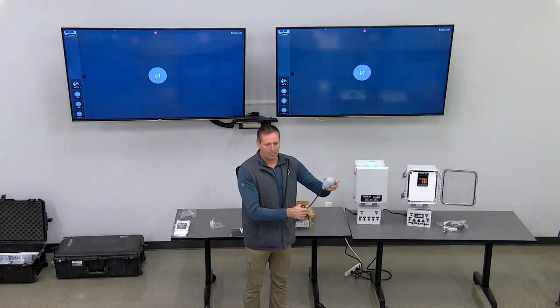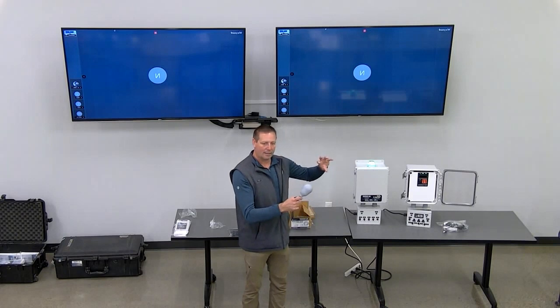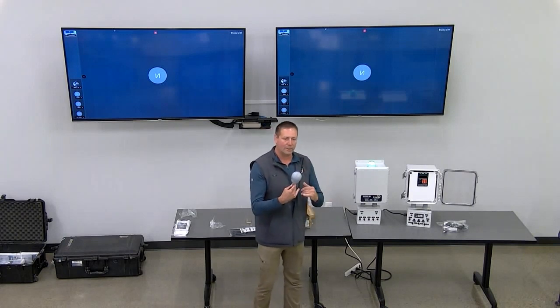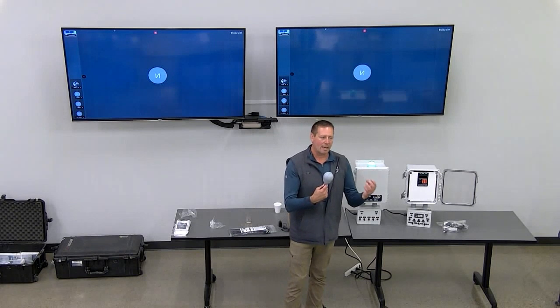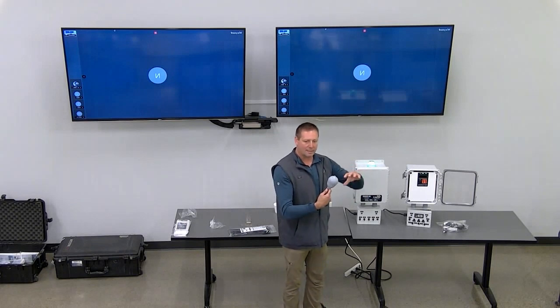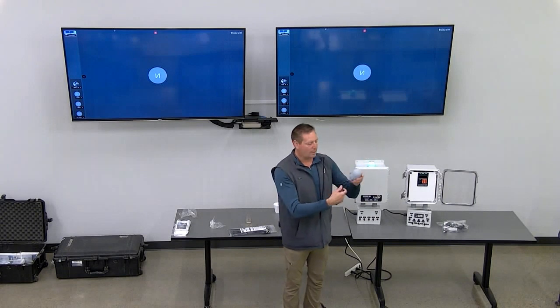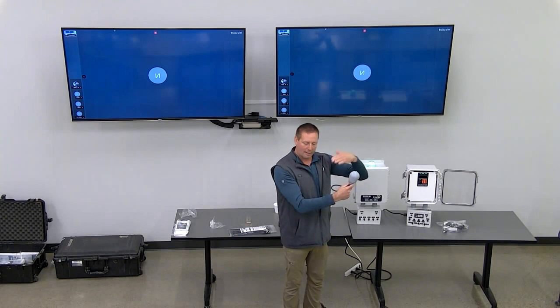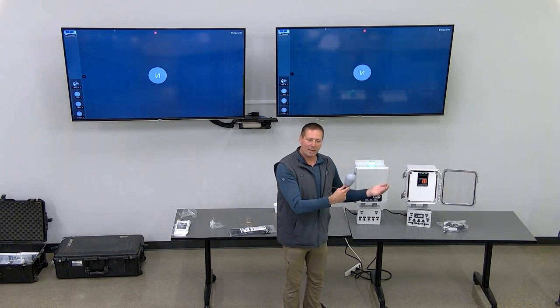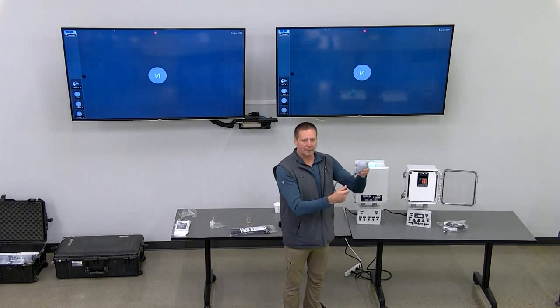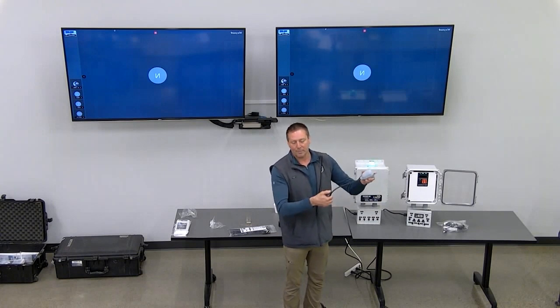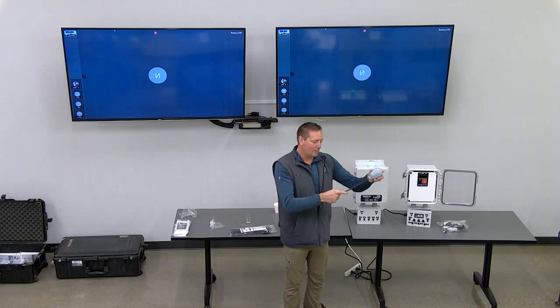So when the float comes up, it closes the circuit, but the pump doesn't start right away. It goes through, and there are mechanical or digital timers, and based off those time settings, you'll typically let the system rest for a predetermined amount of time, maybe 3-4 hours. So even though the circuit is closed, the pump is not running. Once that 3 or 4 hours has elapsed, then the system will turn on and start the pump for 3 or 4 minutes, or it depends on your system, it has to be engineered. I would say typical is like 2.5 minutes, something like that.